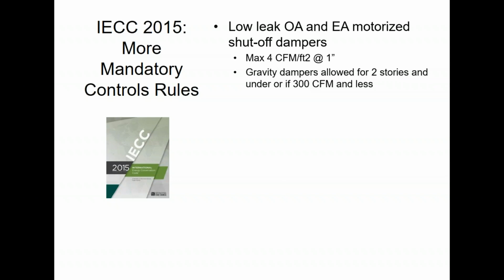In regards to controls, low leak outside air shutoff and exhaust air dampers are required, and they're required to be motorized. If the building's above 2 stories, all those dampers have to be motorized. So from a control standpoint, you need to plan on controlling that. If there's a damper on your exhaust system, it needs to have a motor on it. It cannot be barometric unless it's a short building, less than 2 stories, or it's a really small fan, less than 300 CFM. Economizers dampers always need to have this interlock system.